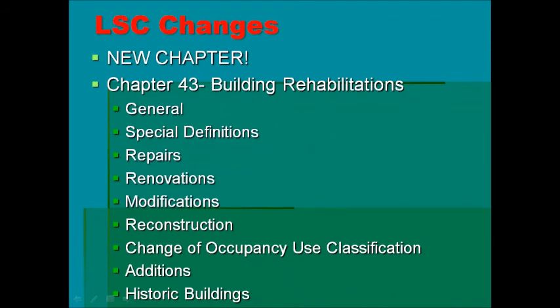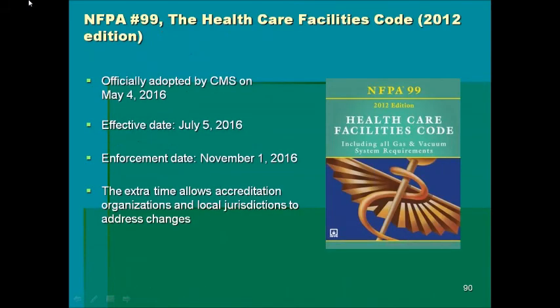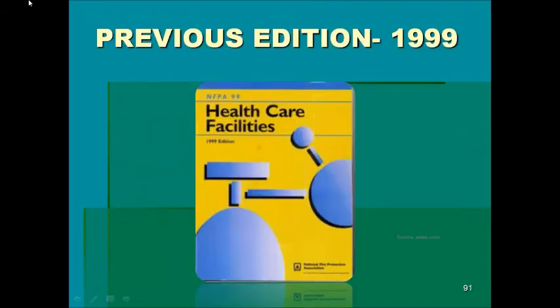The Life Safety Code has also added a new chapter, Chapter 43. It identifies all the things that you need to be familiar with when it comes to building rehab, renovations, modifications, construction, and it even acknowledges historic buildings and the provisions and code changes that apply to those kinds of buildings. In addition to the 2012 edition of NFPA 101, the Life Safety Code, you need to understand that CMS also adopted the 2012 edition of NFPA 99, the Healthcare Facilities Code. And this has some pretty significant implications because there's a new requirement that you need to be aware of if you do any renovation, construction, remodeling, and so forth.